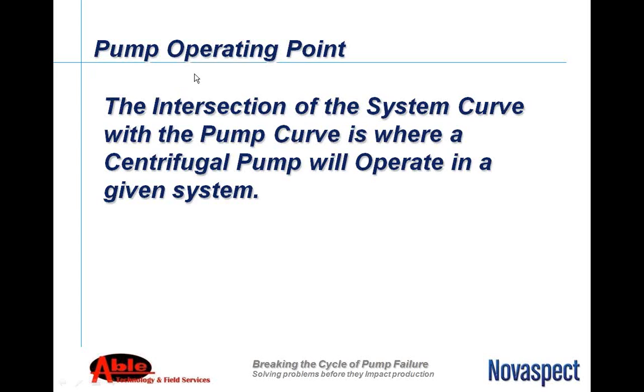So we're going to talk a little bit about the pump operating point. The intersection of the system curve with the pump curve is where the centrifugal pump will operate in a given system.